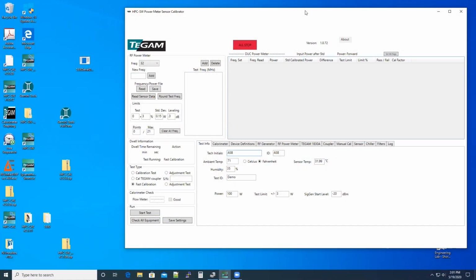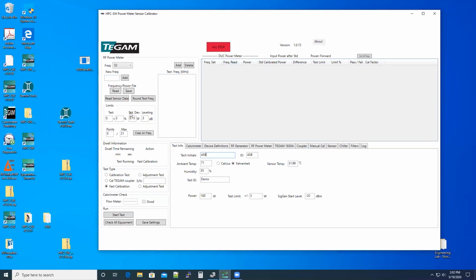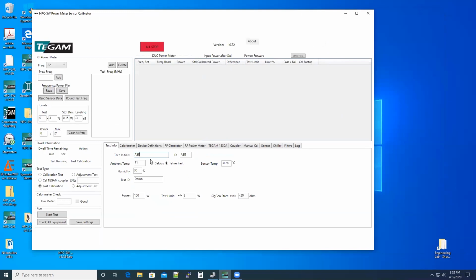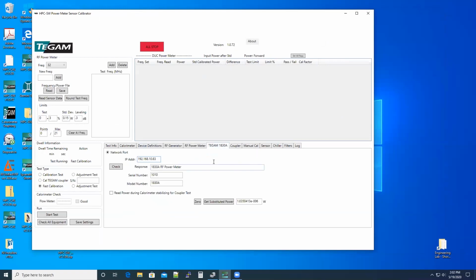So for our first task, we're going to test this Bird sensor and get a cal report for it. So let's go look at the software that's going to run that. We're going to use the software HPC SW. I need to move this over a little bit. So to get the software going, the first thing I'm going to do is make sure that I have all my instruments attached to it. So my TEGAM 1830A, it's connected over Ethernet. I've checked it already, but I can read it.